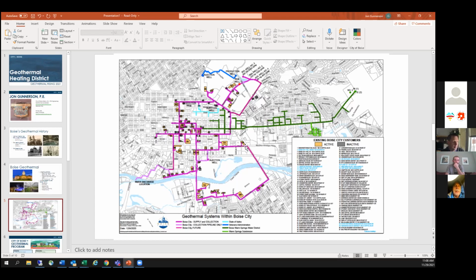The water that we pump, let me walk through our operation here. Everywhere that you're seeing a pink line on this map, there's actually 2 pipes. So this is a 2-pipe system where we're pumping the water from one of the 3 production wells. We're piping it to one of the 96 buildings, in which they use heat exchangers, plate and frame heat exchangers typically, to extract heat off of this water. The water that we're pumping out is 177 F, about 81 C.